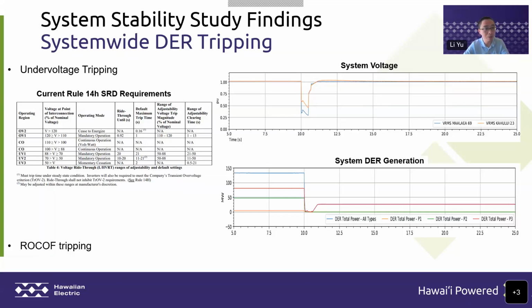So in our tariff, for the post-2016 DER, we have 0.5 per unit undervoltage trip as a minimum. We can accept the 0.5 second clearing time, and meanwhile we have zone 2 tripping in our transmission level fault, so that clearing time can also last to 0.5 seconds. That basically means if there's a fault on the transmission system and the clearing lasts 0.5 seconds, then we're going to see a large chunk of DER get tripped because of the undervoltage issue.